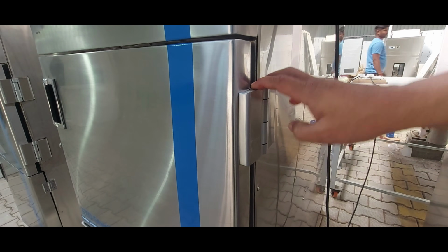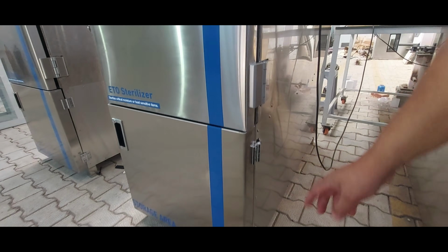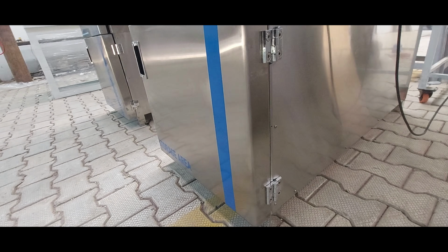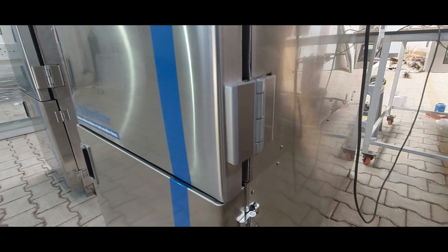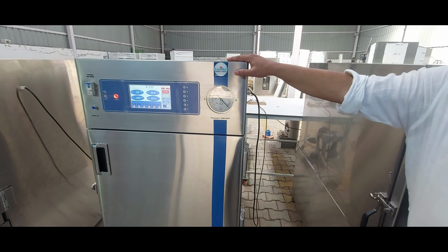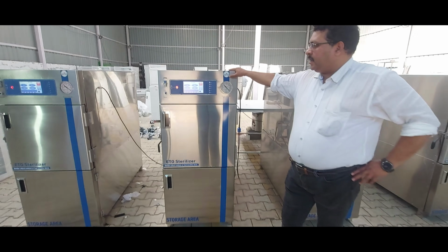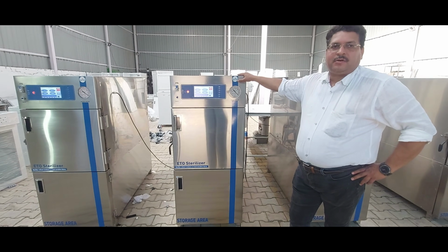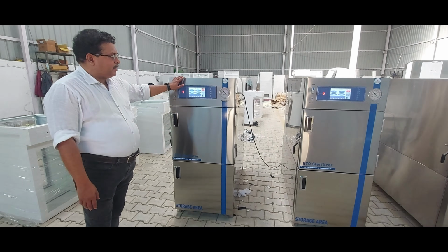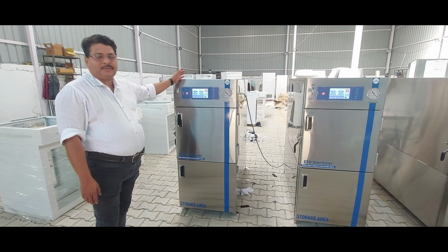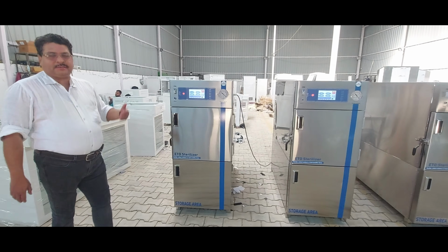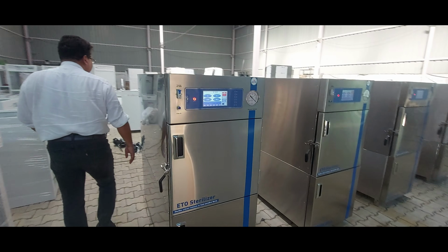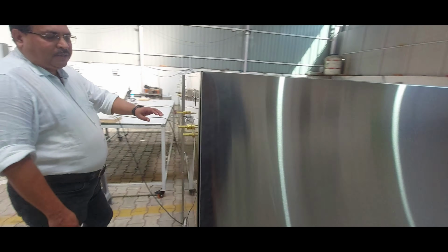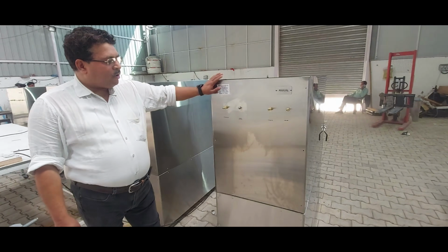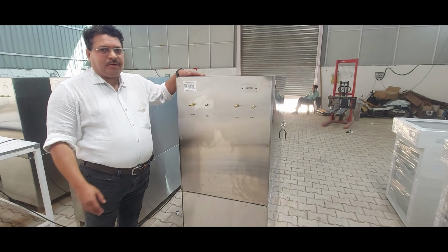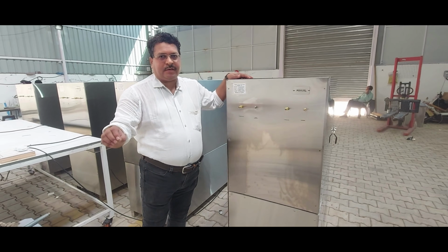Important considerations. Process validation. ETO sterilization processes are rigorously validated using biological and chemical indicators to ensure safety and compliance. Product compatibility. The ETO sterilization process and its parameters are carefully studied to ensure safety and effectiveness for different types of medical devices and packaging materials. Residual EO removal. Proper aeration and degassing cycles are crucial to remove residual EO gas after sterilization to minimize any potential risks. Standards. The ISO 11135 standard provides guidelines for developing, validating, and controlling ETO sterilization processes for medical devices.